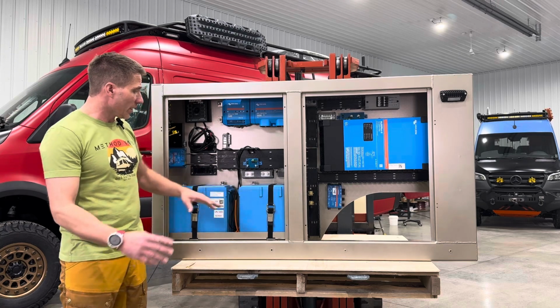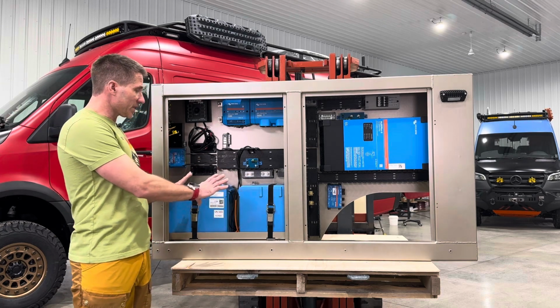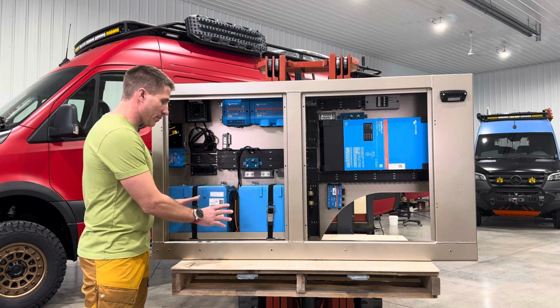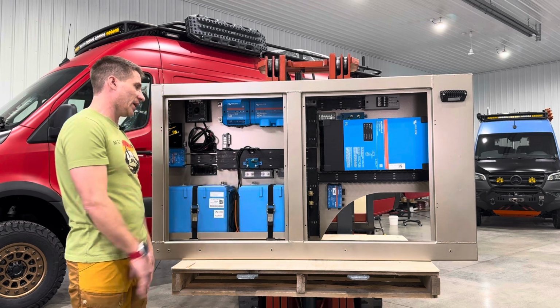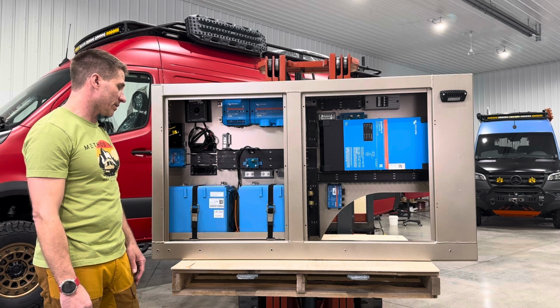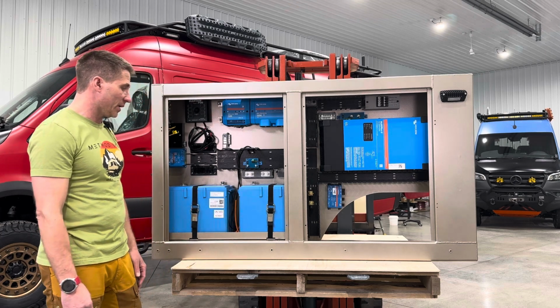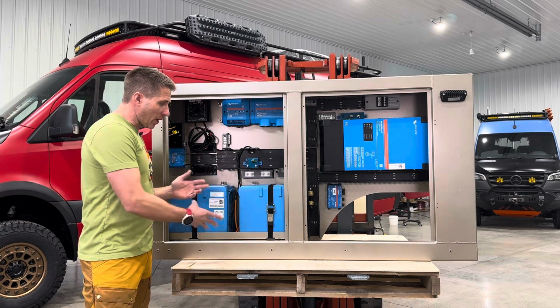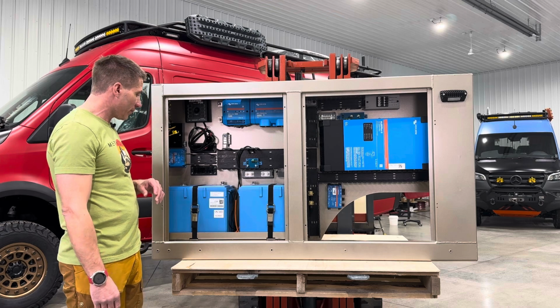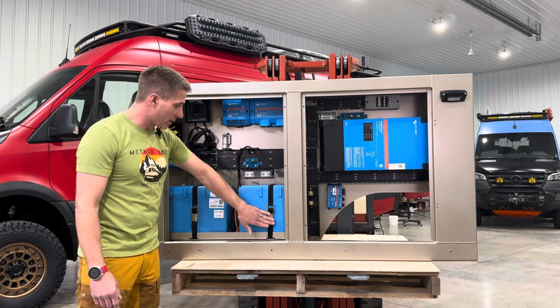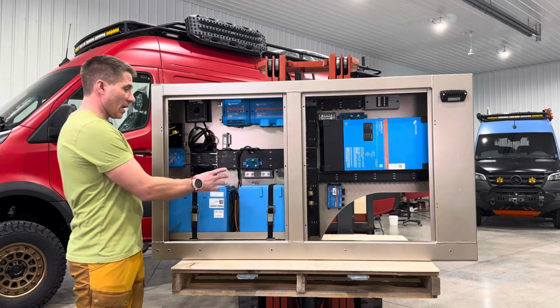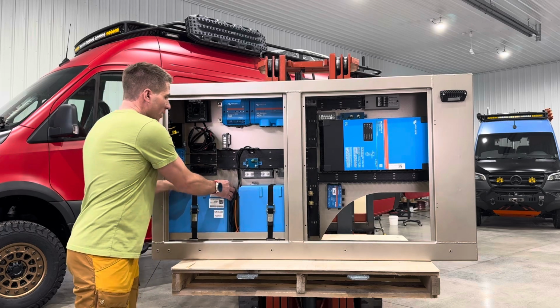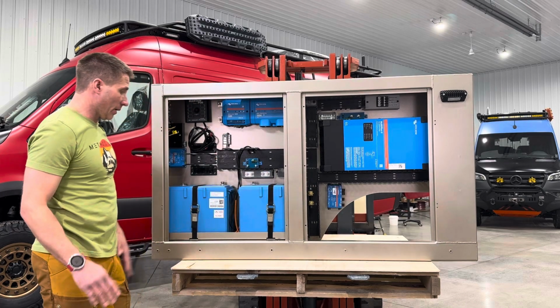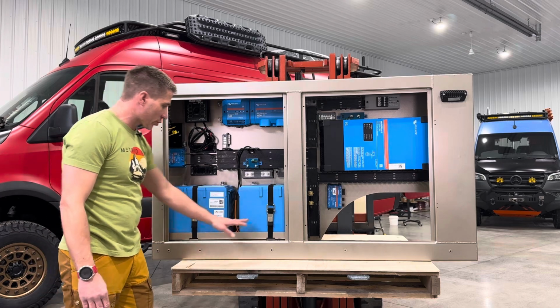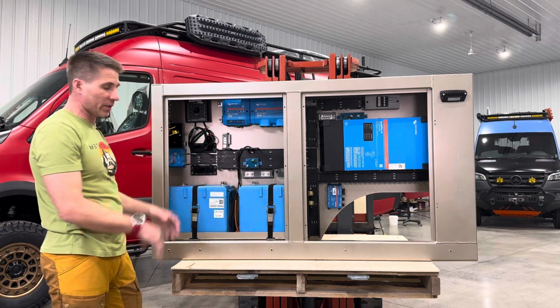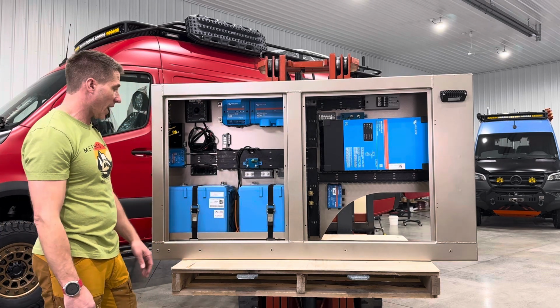We call this a fully heated battery system, in that the pads are generously heating the batteries themselves. With the thermal break in the battery guard, we're not getting much loss of heat into the cabinet itself. These are attached with marine grade latching systems and are rock solid - they are not going anywhere. It's all held through this battery tray, which is bolted with six quarter-inch bolts into the base of the cabinet.